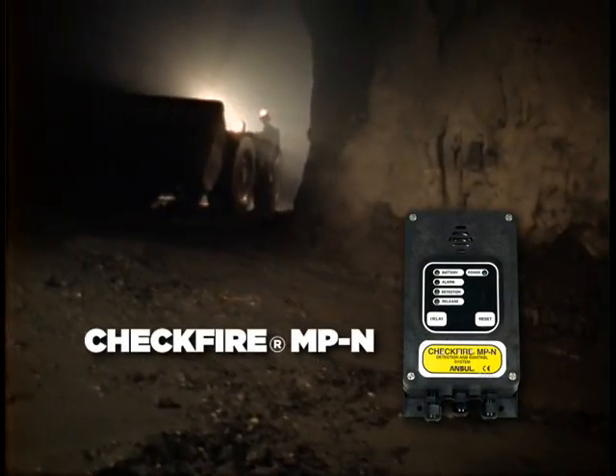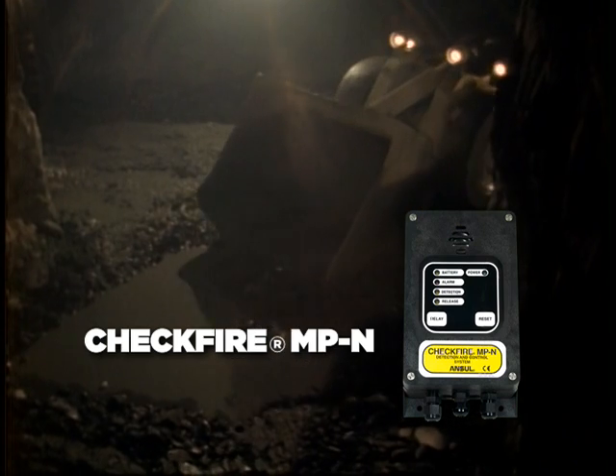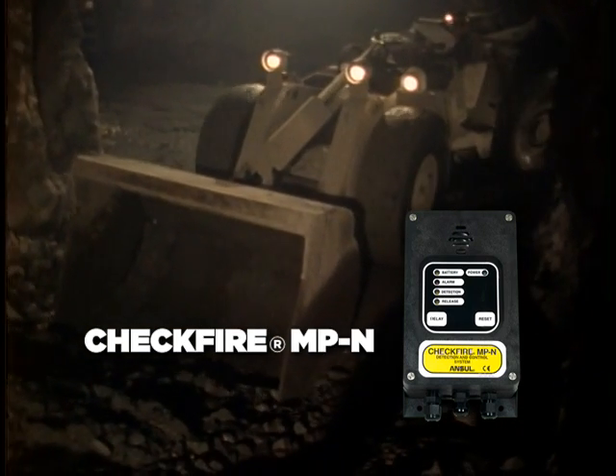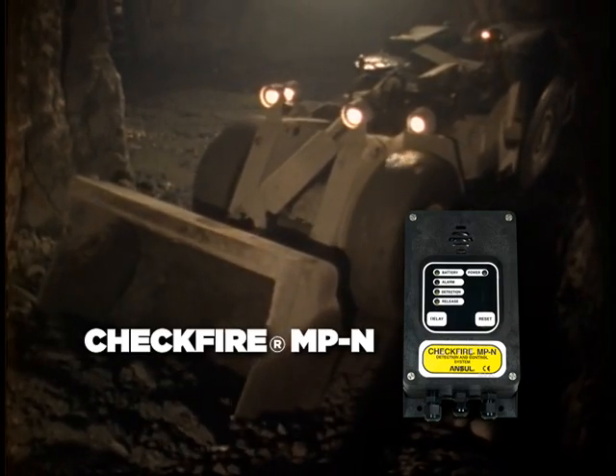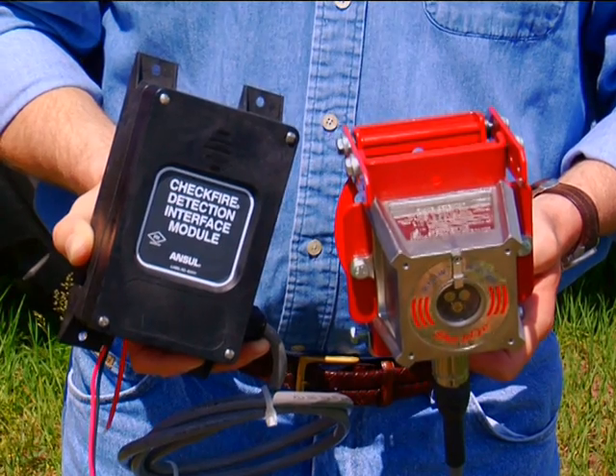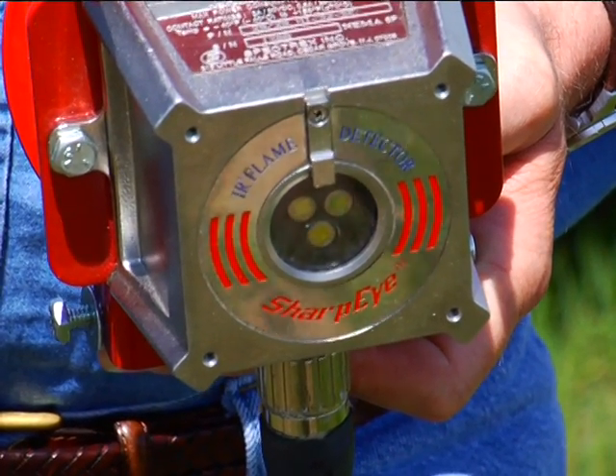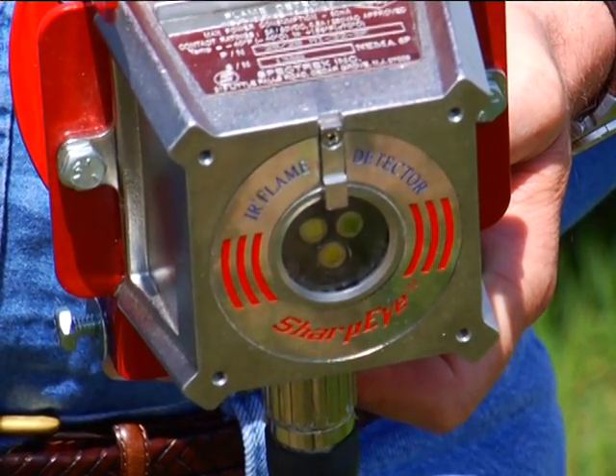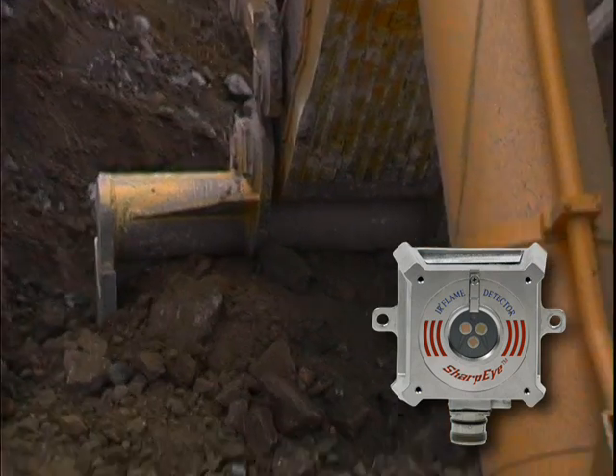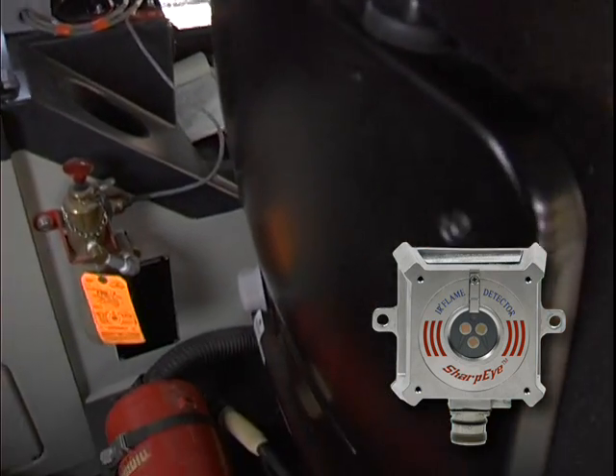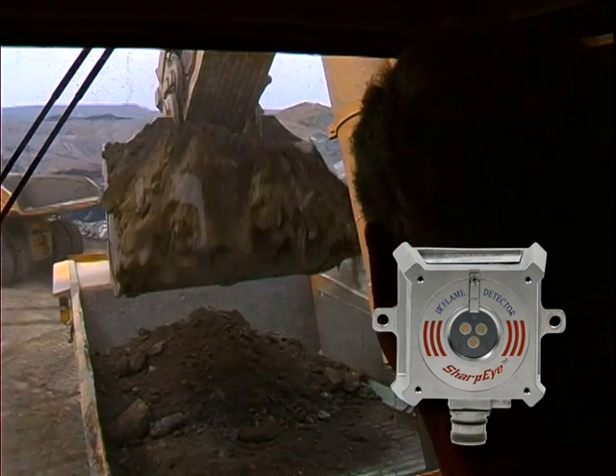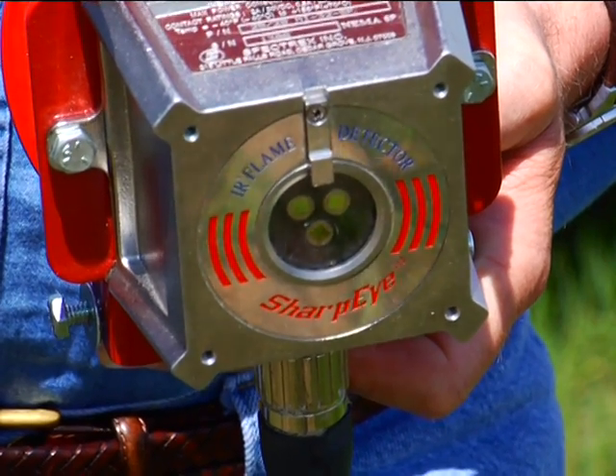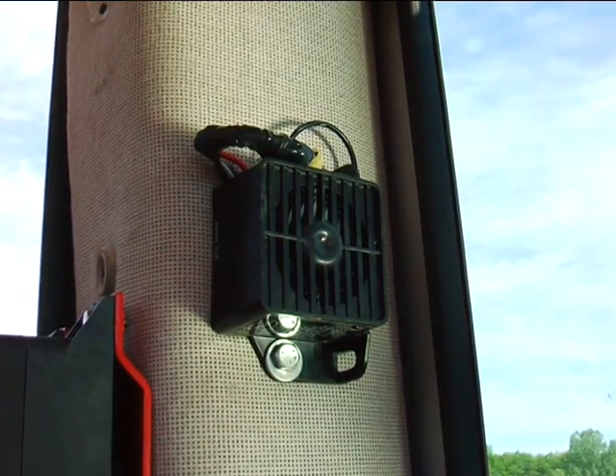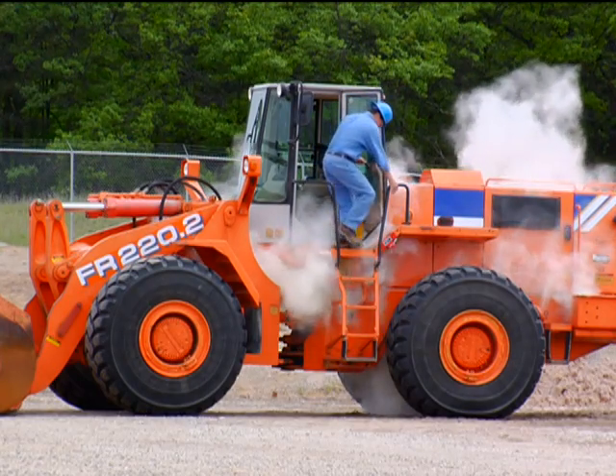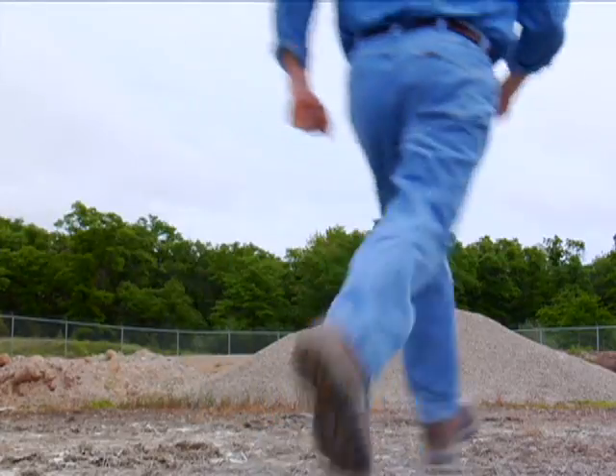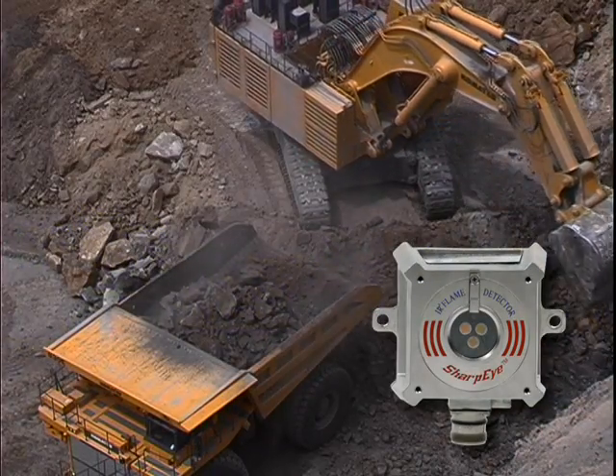Check Fire MPN, or mine permissible model, offers all the same features, plus MSHA approvals for underground mines. This makes the Check Fire MPN permissible in possible explosive gas environments. For optimal protection, add the FM-approved SharpEye Triple IR flame detector to the Check Fire detection and actuation system. This system has been designed specifically for use in the mining industry to provide additional fire detection in extreme conditions. Ansul SharpEye Triple IR detection reacts in seconds, triggering the Check Fire module and signaling the operator to evacuate the machine. Given the cost of today's new machinery, this improved detection speed can further limit fire damage. The SharpEye Triple IR detector is a heavy-duty detection system with added resistance to false alarms.